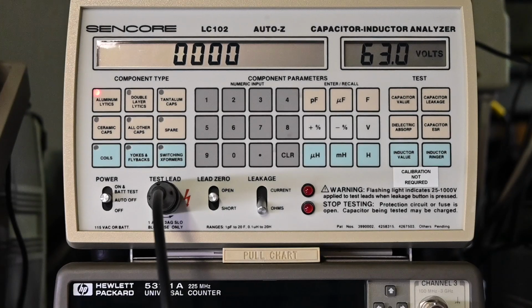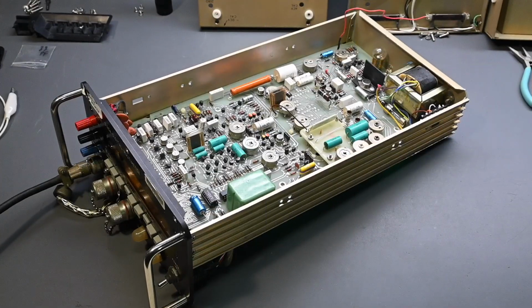So I hope this gives an idea of the different ways that you can test a capacitor, and ultimately knowing the leakage test on a capacitor, the leakage current, or ultimately you can convert it over to the resistance across the capacitor, and really how important that is in determining if a capacitor is usable or not. All right, so this concludes part 1 on the Fluke 8125A digital multimeter troubleshooting and repair.